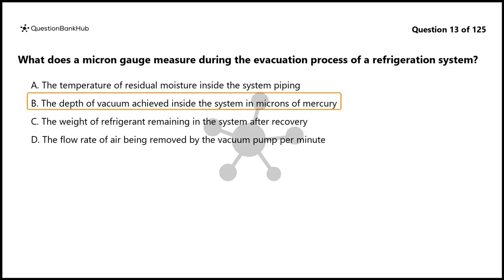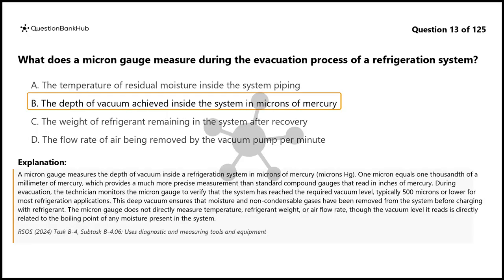The correct answer is B. A micron gauge measures the depth of vacuum inside a refrigeration system in microns of mercury, microns Hg. 1 micron equals 1,000th of a millimeter of mercury, which provides a much more precise measurement than standard compound gauges that read in inches of mercury.